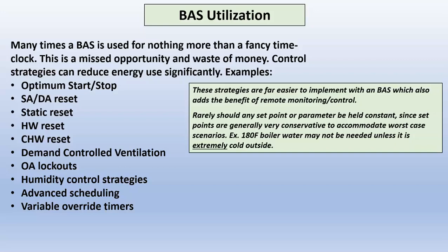And on the other side of that is Optimum Stop. And what that does is take advantage of the thermal inertia of the building. Let's say the algorithm says, I'm scheduled till 5 o'clock. It's 4:30. I've got enough in this building right now that I think I can coast the next half hour. And it'll stop the system based on that.